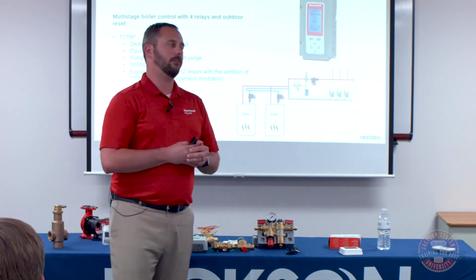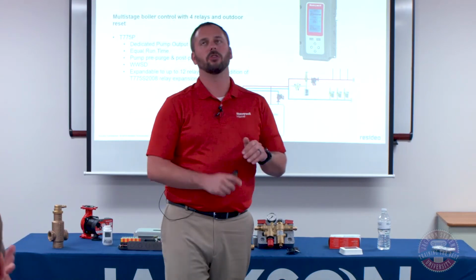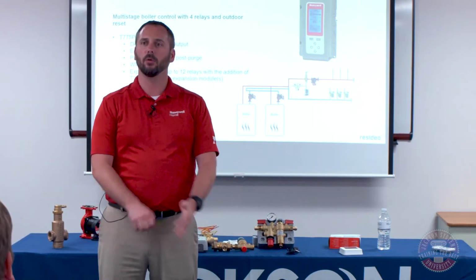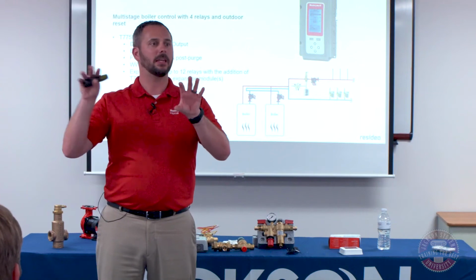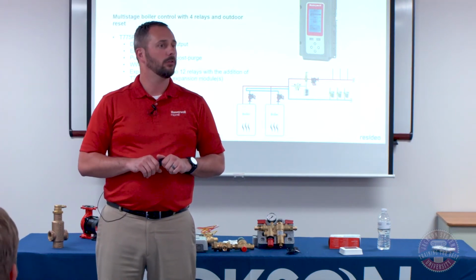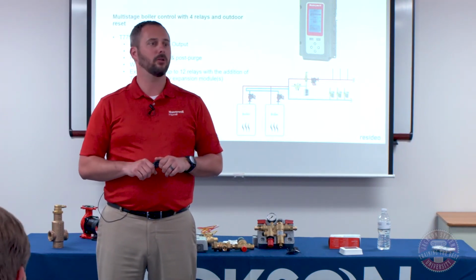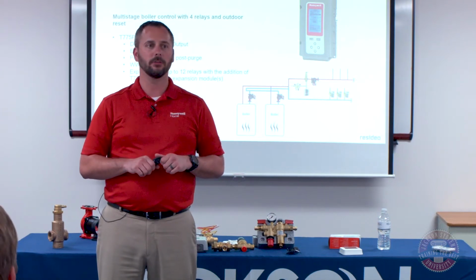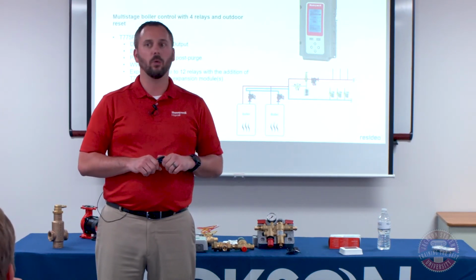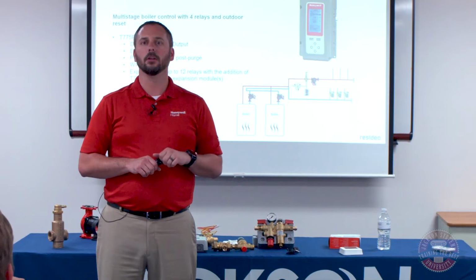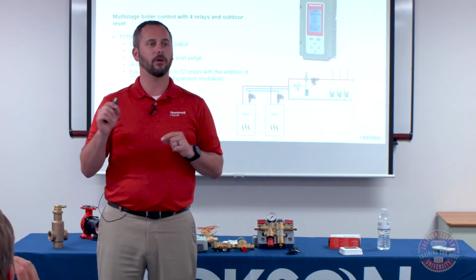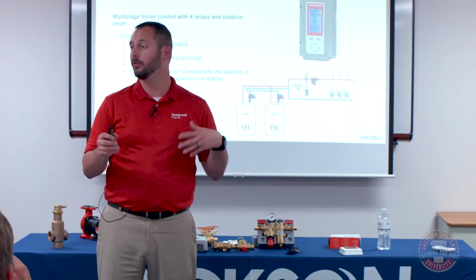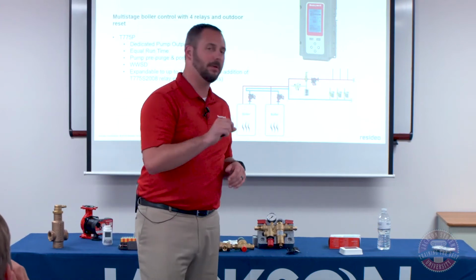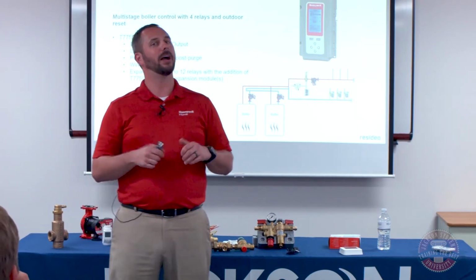I have used these on jobs where we've got up to like 5 or 6 boilers. You can basically expand it and keep them daisy chained all the way through. So if you've got two copper fin, two cast iron, we see that a lot in commercial jobs because of two reasons. One, you want redundancy, and two, you need the lower firing rate to eliminate some of the short cycling as well. So you can get to a lower firing rate as well.